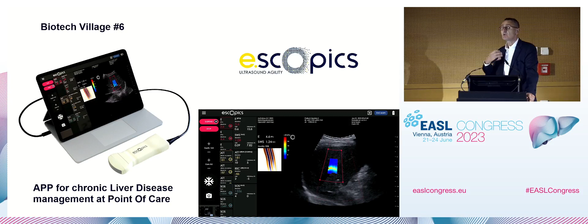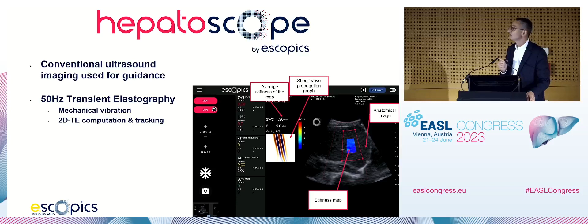The way it works is that it provides an ultrasound image where you locate a region of interest, and then you apply the probe between the ribs. The probe vibrates, sending a 50 hertz vibration, which is called mechanical transient elastography, and this mechanical vibration propagates in the liver. But the beauty of an imaging system instead of a single element is that you are able to map this propagation in 2D, and at every point on the propagation map, you're able to measure the stiffness.